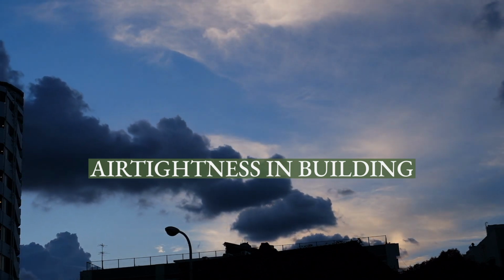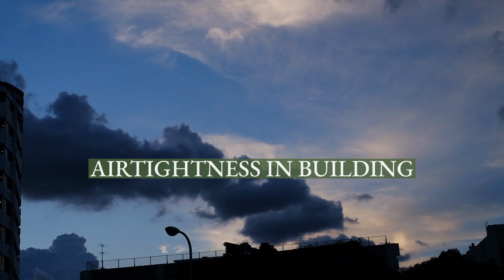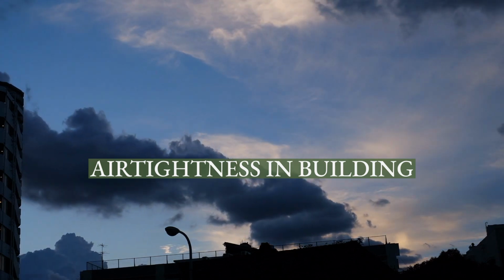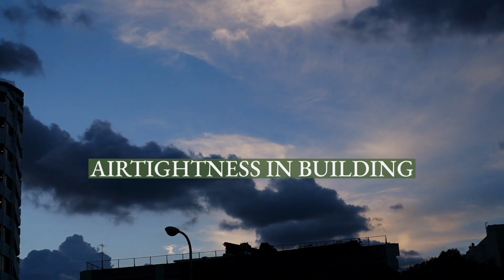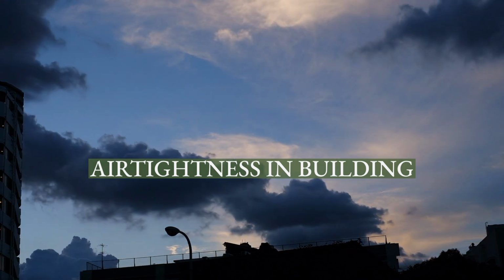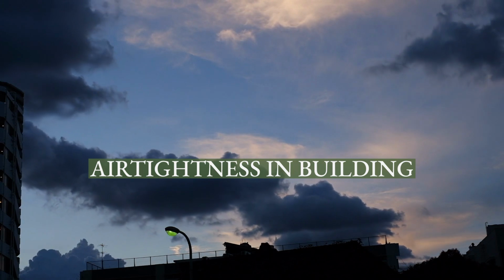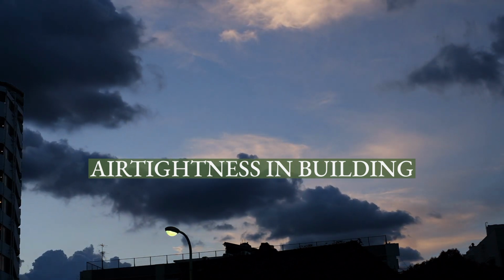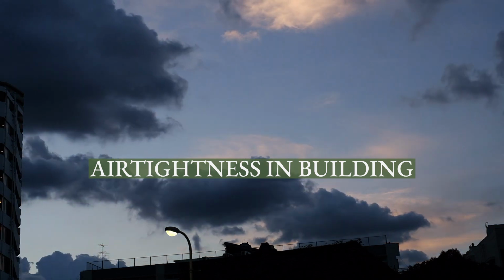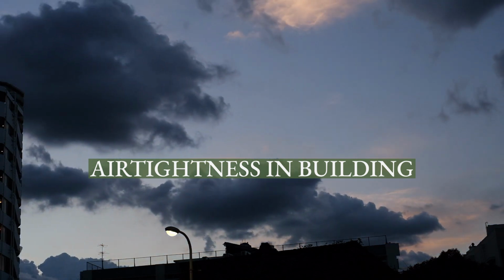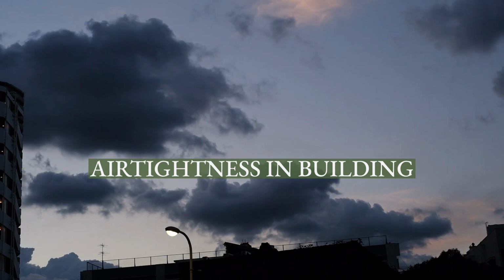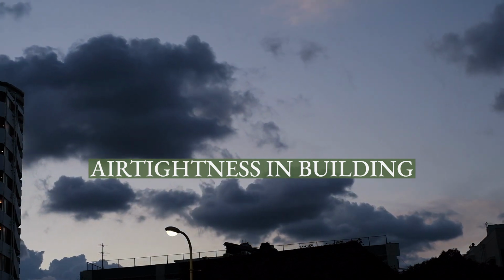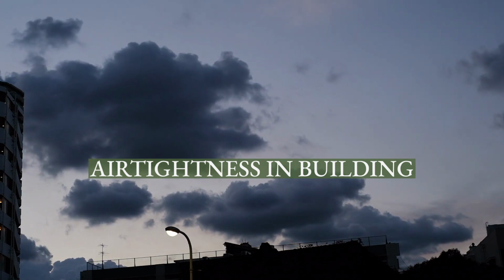For this reason, the Passive House Standard established performance requirements for airtightness, requiring less than 0.6 ACPH with a pressure difference between inside and outside of 50 Pa. It is worth noting that ACPH measured with the blower door test at a differential pressure of 50 pascals mimics the situation of a sustained 20 miles per hour (32 km/h) wind outside.